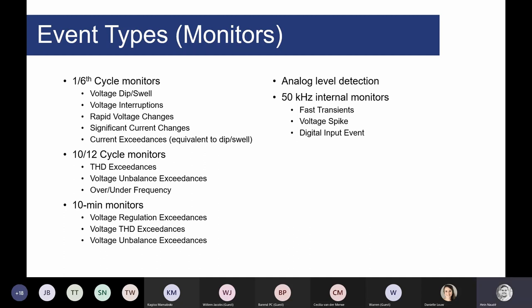The last sort of monitors we have are the 50 kilohertz ones. For example, the fast transients take the raw waveform data and put it through a very steep cutoff filter to filter out the 50 hertz component. You then end up with a signal that only contains the high frequency components. On that high frequency component, you put a threshold, and when that threshold is exceeded, it basically triggers as the fast transient.